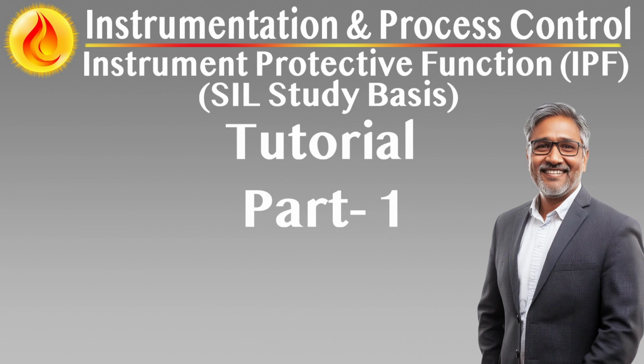Hardware configuration and redundancy requirements. IPFs require hardware architectures that ensure fail-safe operation under fault conditions. Redundancy strategies such as 1oo2, 1 out of 2, or 2oo3, 2 out of 3 voting must be used where dictated by the SIL or risk tolerance.